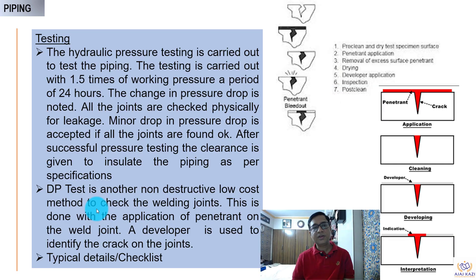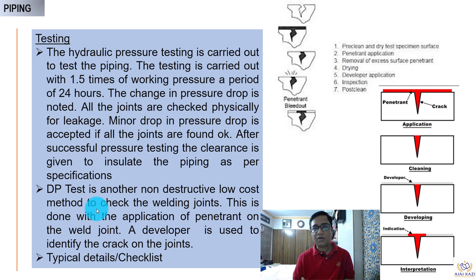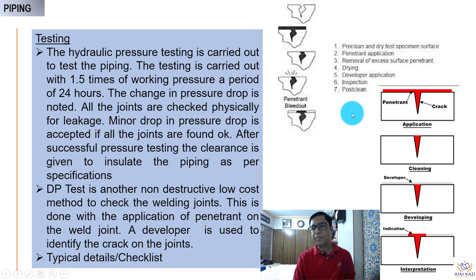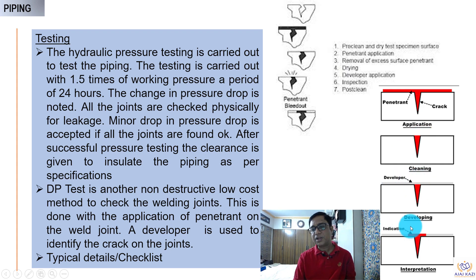When the entire piping is done, testing has to be performed. Generally, testing is done at 1.5 times the working pressure for 24 hours. Another quick method is the DP (dye penetrant) test — apply a penetrant, and if there is a crack, apply the developer. After inspection, if there is a red indication, there is a crack.